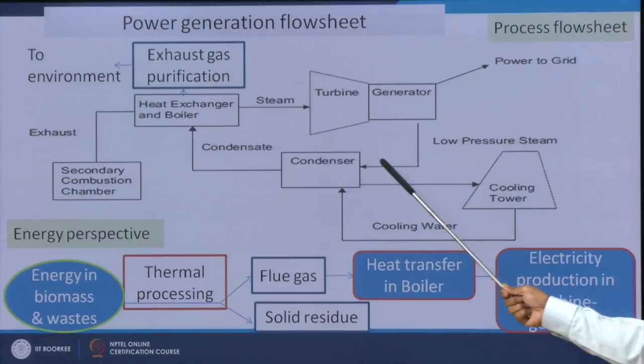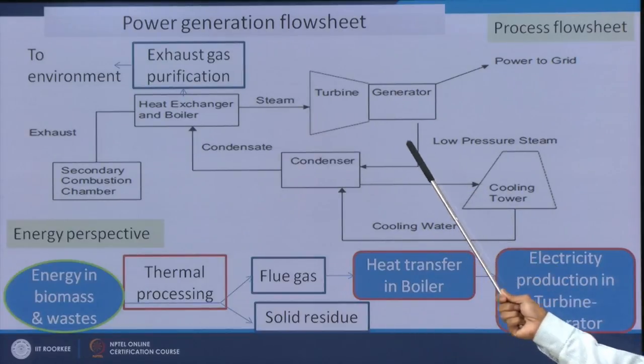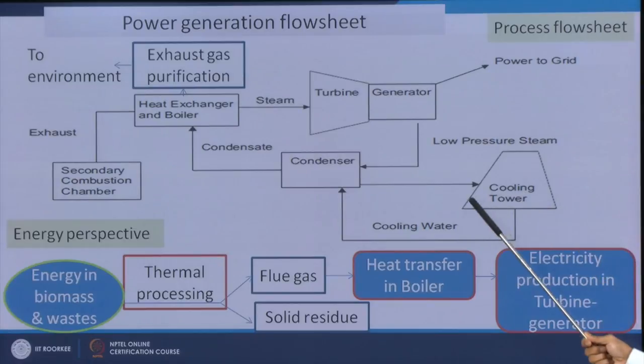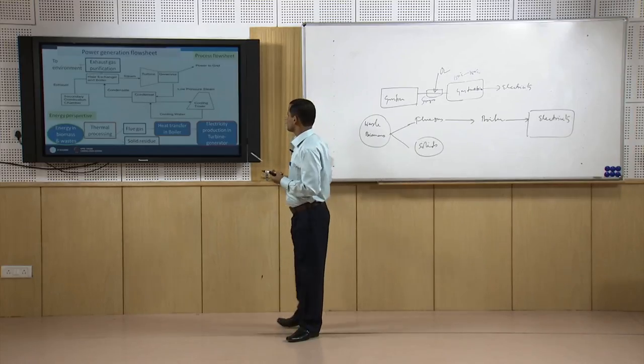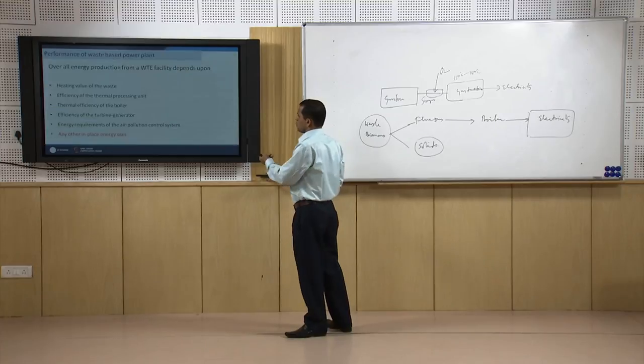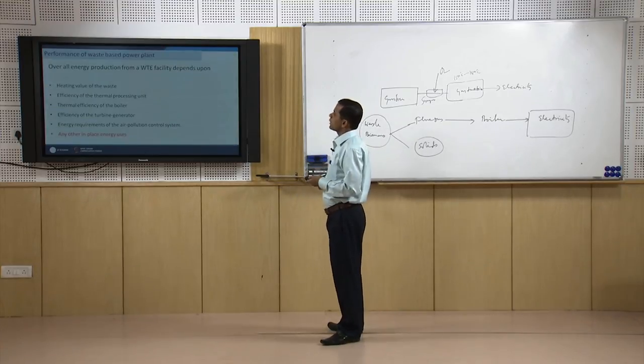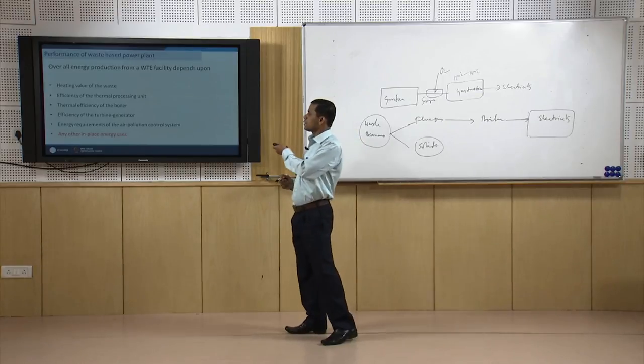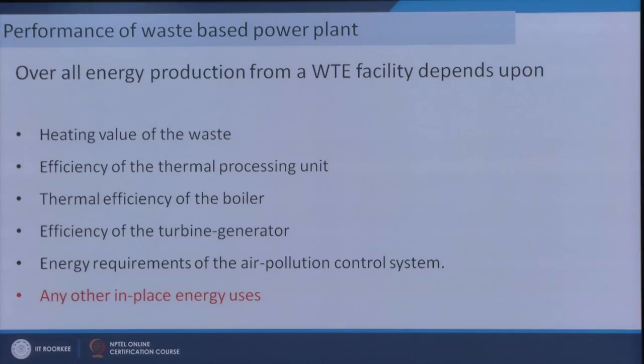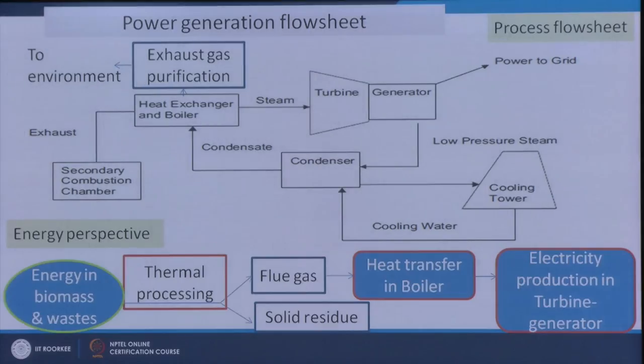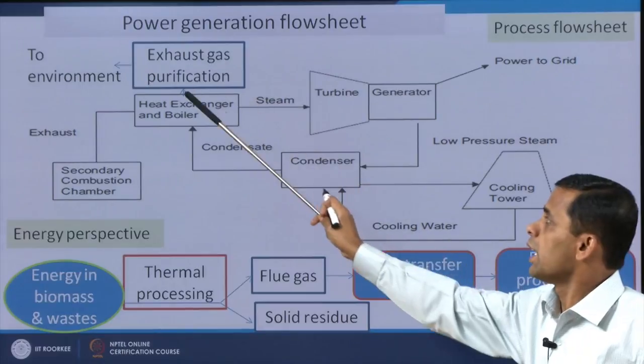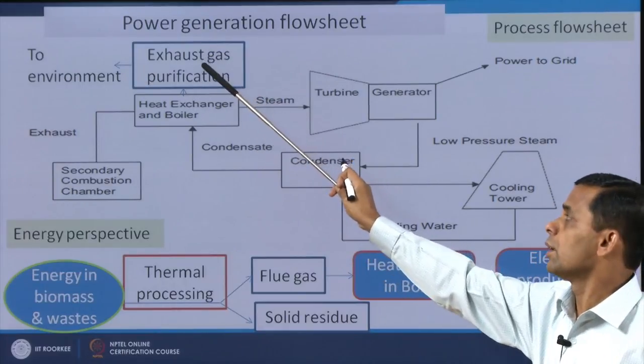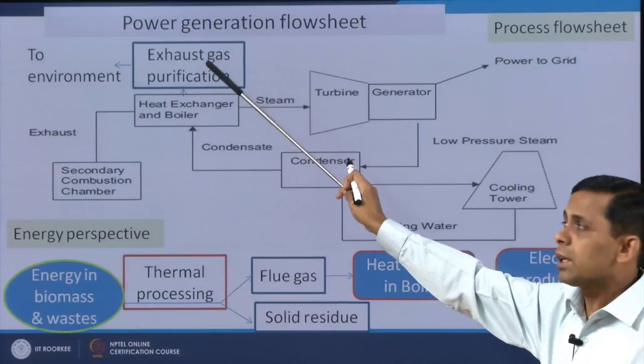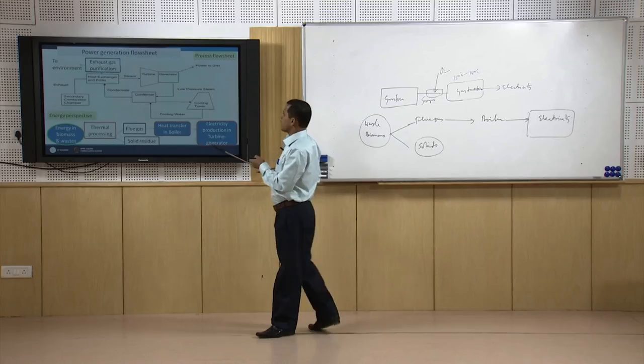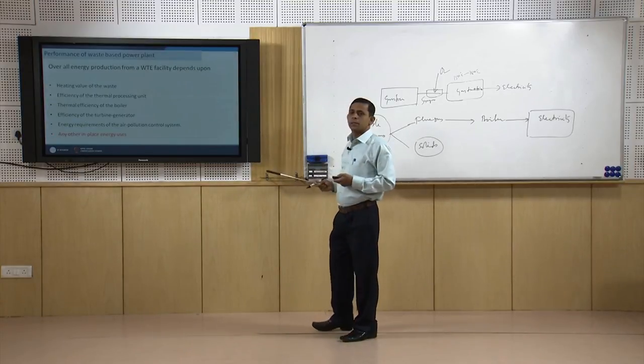Whether the heat available at the outlet of the turbine is used for heat recovery or not will also influence the overall performance of the process. So these are the heating value of the waste, efficiency of the thermal processing unit, thermal efficiency of the boiler, efficiency of the turbine generator, energy requirements of the air pollution control system. The air pollution control systems treat the exhaust before it goes to the environment, so the amount of energy required for that also influences the overall performance of the process, along with any other in-plant energy uses.